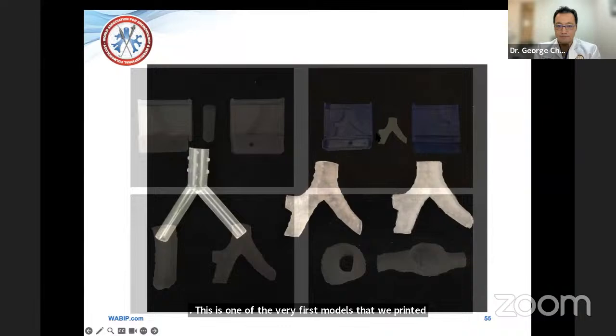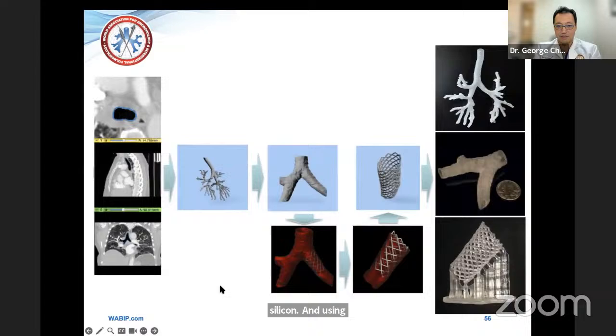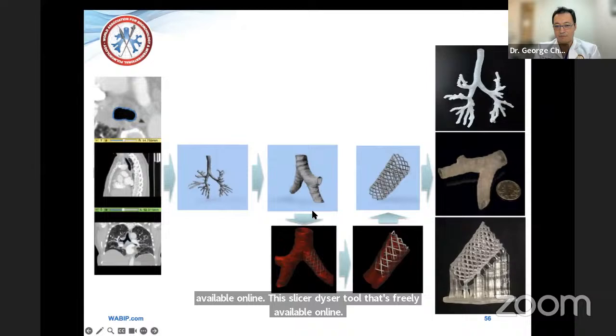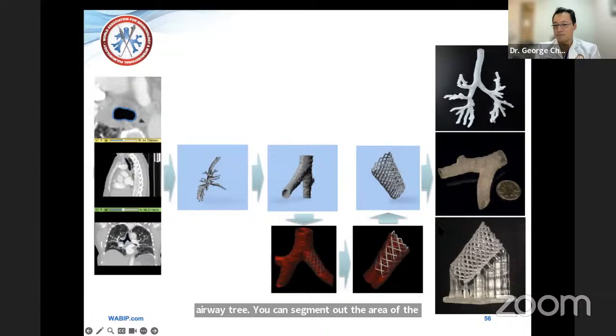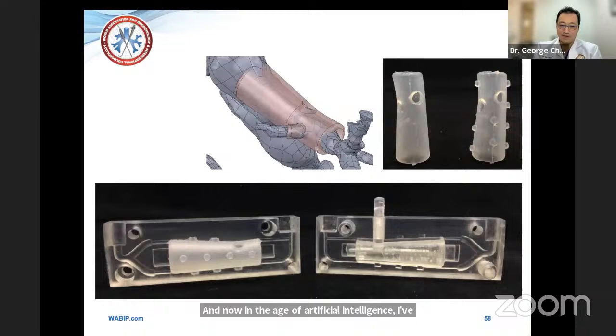We were able to go from a traditional Y stent to a printed plastic airway model to an injection molded silicone stent. Using this slicer dicer tool that's freely available online, you can do airway segmentation of the entire airway tree. You can segment out the area of interest, then feed it into a variety of CAD models and start designing different airway shapes or stent shapes based on those models. This is one of the different models we were able to generate in one afternoon. Now, in the age of artificial intelligence, I imagine this would be 5 minutes of work instead of an entire afternoon.